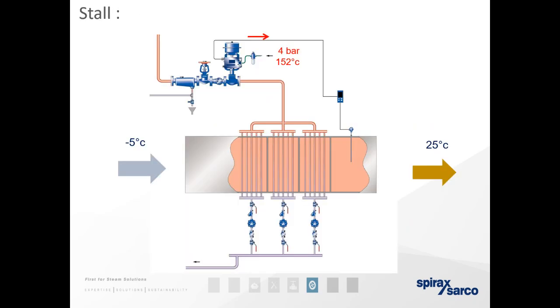So an example of stall here, we've taken an air handling unit, but this could be a heat exchanger, it could be a coil, it could be anything. As you can see, you have your separator, your isolation valve and control valve at the top left hand of the picture. Hopefully you can see my laser. In this particular case, we've got 4 bar, and that's 152 degrees. So as steam enters the system, it comes into the coils, air passes through, picks up the transfer of heat through the enthalpy, and then it turns to condensate and is removed by the traps and sent back to the system.